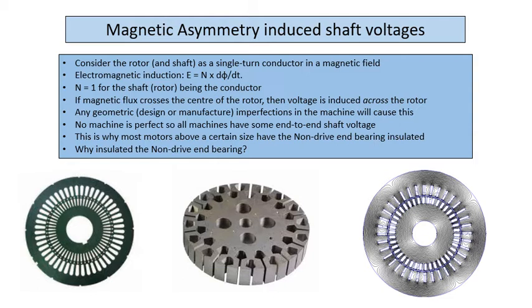Why is it the non-drive end? Because typically you've got control over the non-drive end, nothing's connected to it. You never know what's, well, you should know, but typically the drive end will be earthed via the driven equipment. It's got all its own issues. So you insulate the side that you have control over.